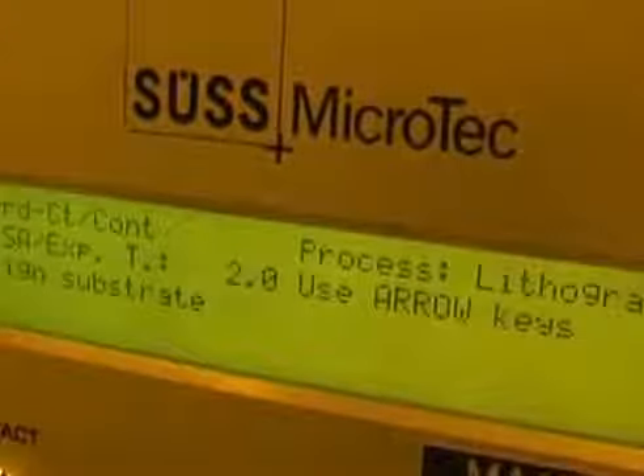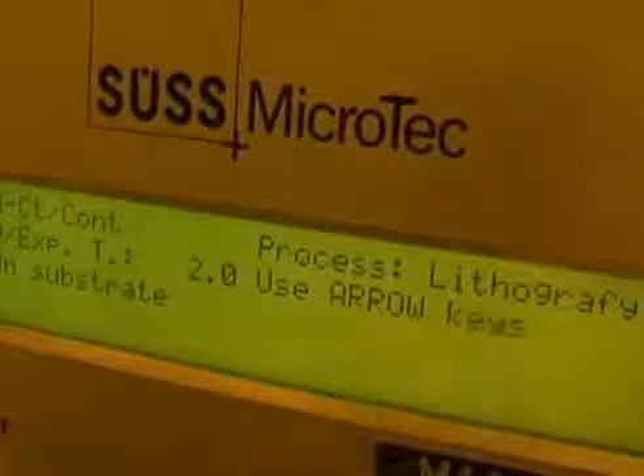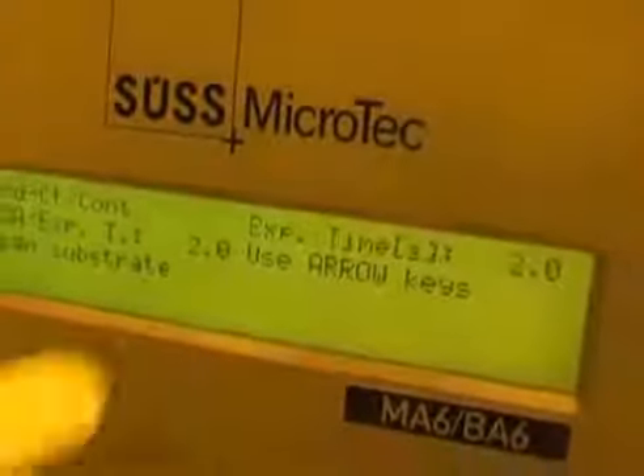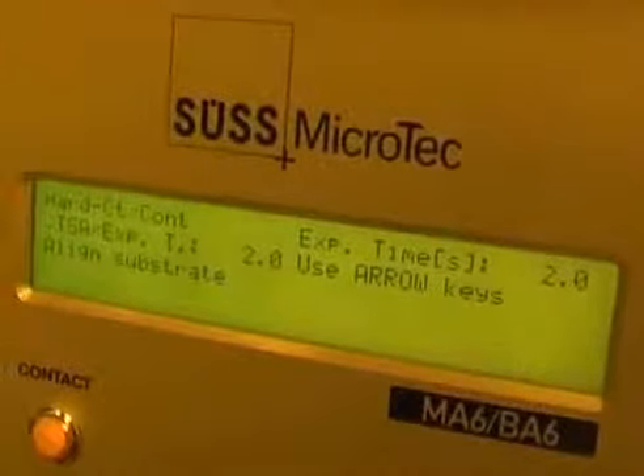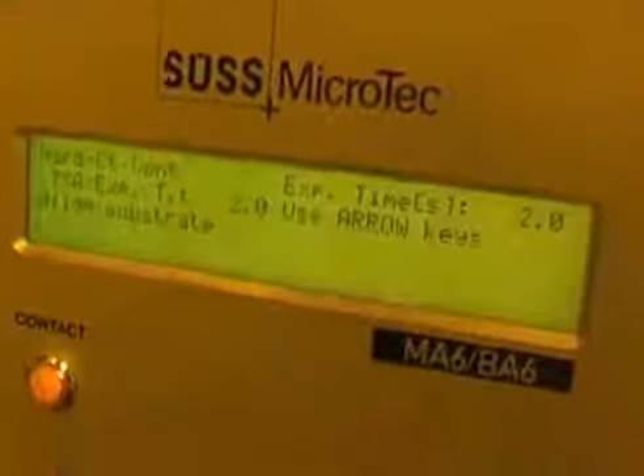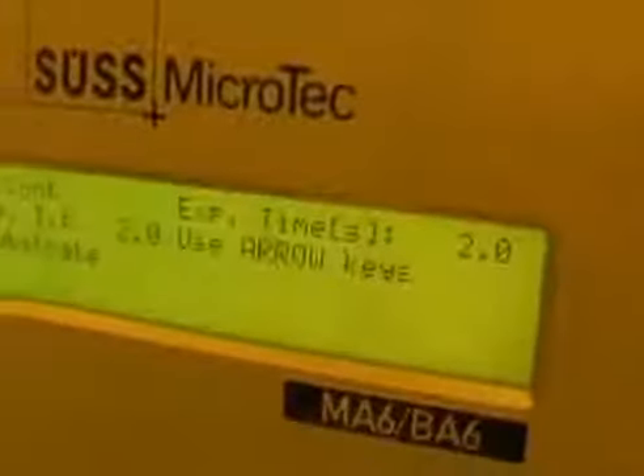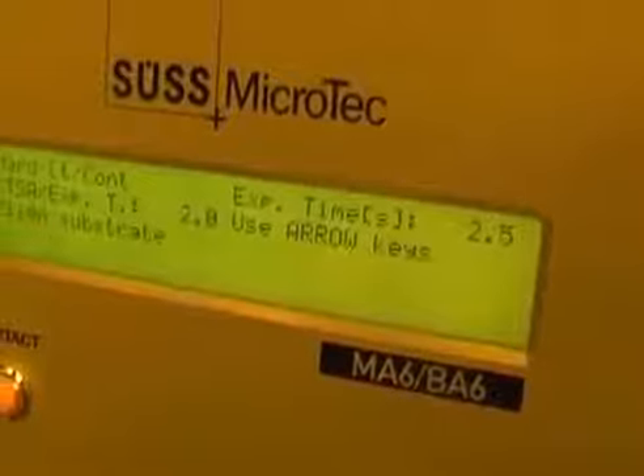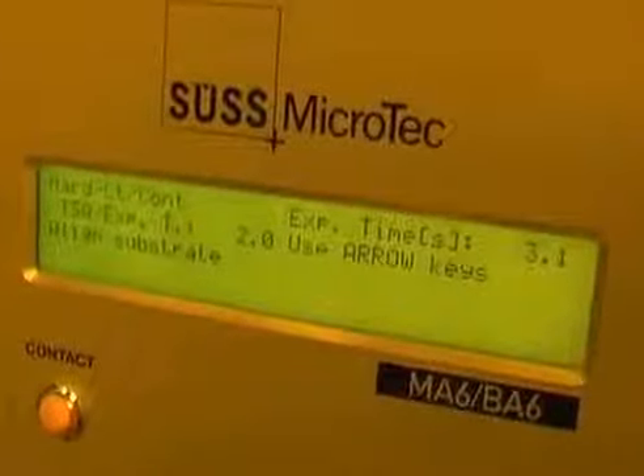To set the exposure, we press edit parameter, and again using the arrow keys we scroll through our options. We're set up for a lithography process, so we move along. We're asked to set the exposure time. For this particular resist, which is 1818, we will set an exposure time of 4 seconds. So we're set at 2 seconds and we want to move up. We use the up arrow. Again, to confirm the exposure, we depress the edit parameter to store the information.